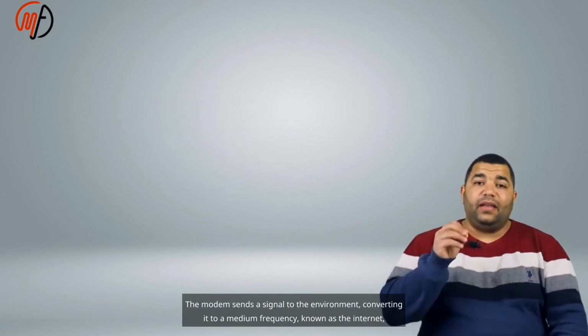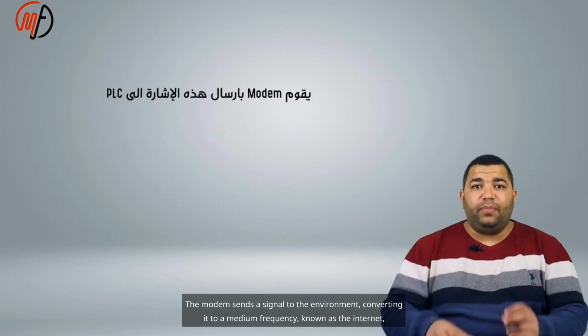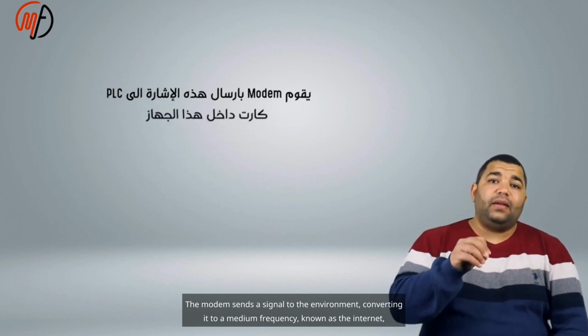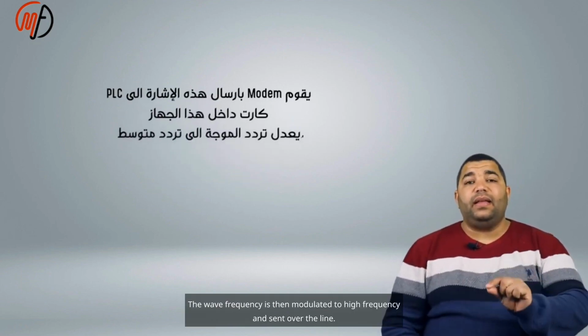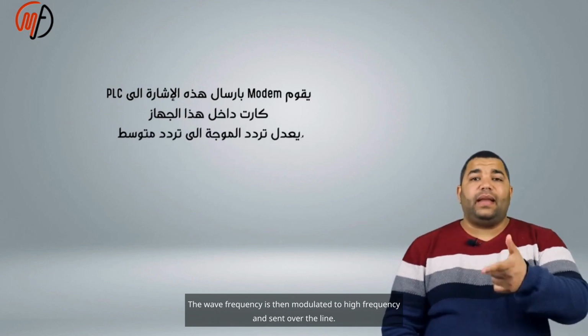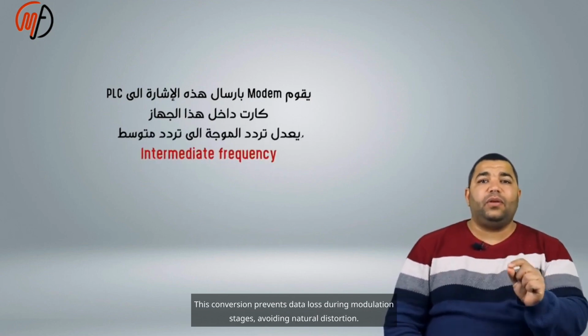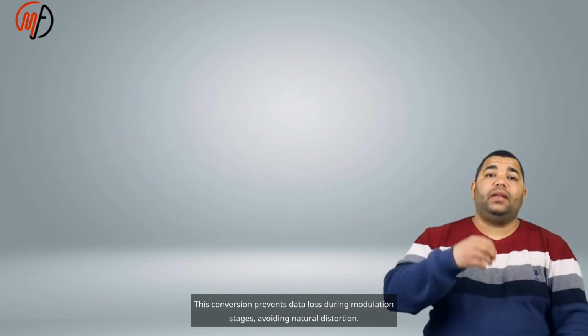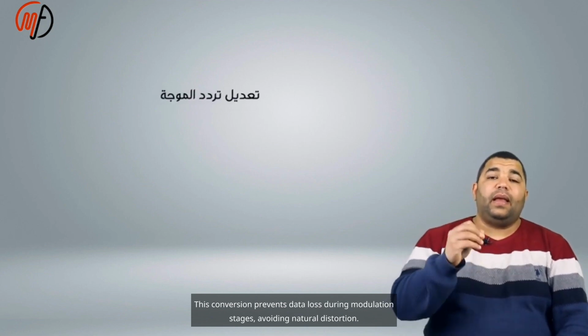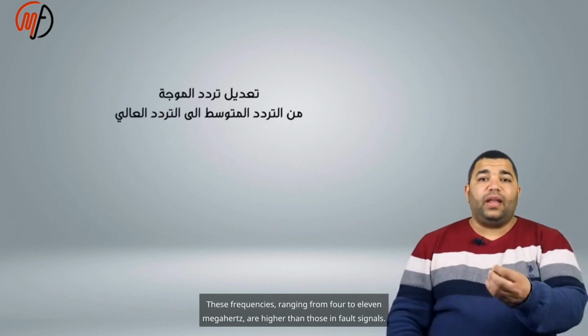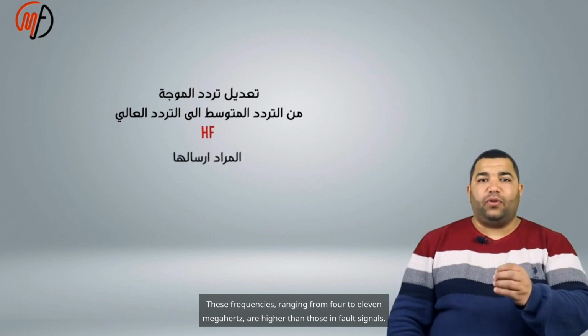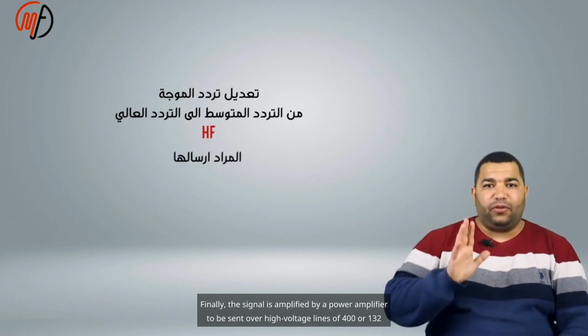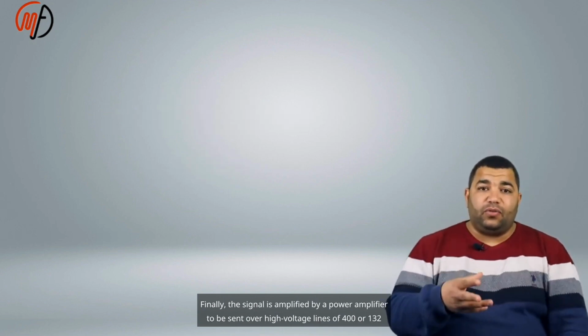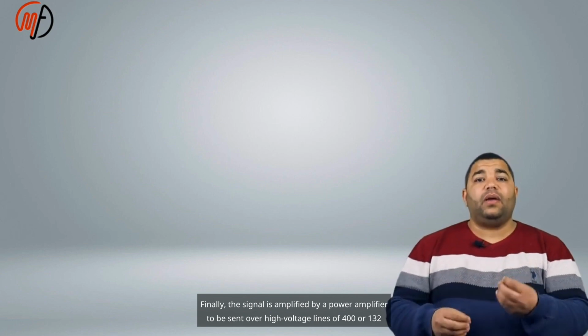The modem then converts the signal to a medium frequency, known as the intermediate frequency, through a device card. The wave frequency is then modulated to high frequency and sent over the line. This conversion prevents data loss during modulation stages, avoiding natural distortion. These frequencies, ranging from 4 to 11 megahertz, are higher than those in fault signals.